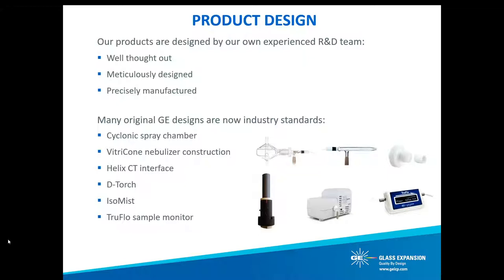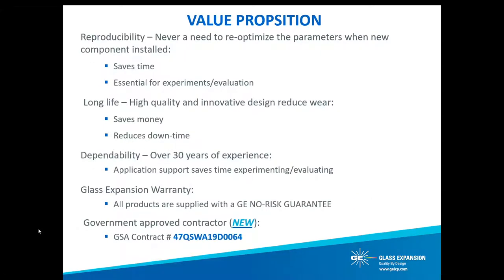As we all know, the nebulizer is a critical component of your ICP sample introduction system, and therefore you need to make the right choice to get the best results out of your instrument. Before we focus on nebulizer selection criteria such as efficiency, impurity, and tolerance, let's quickly address the importance of quality. Physical nebulizer design reproducibility saves the analyst time as they never need to re-optimize nebulizer parameters when the nebulizer is replaced. Glass Expansion's line of nebulizers follows strict manufacturing guidelines and QC inspection, in addition to careful selection of raw material, so that each nebulizer is manufactured with the highest physical reproducibility.